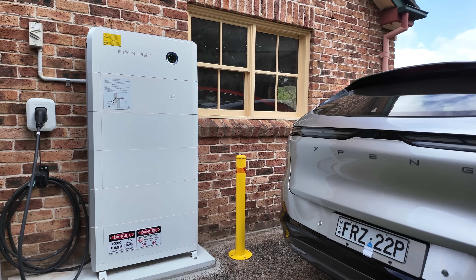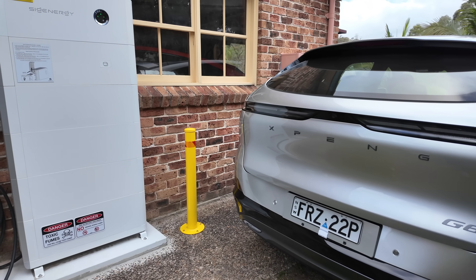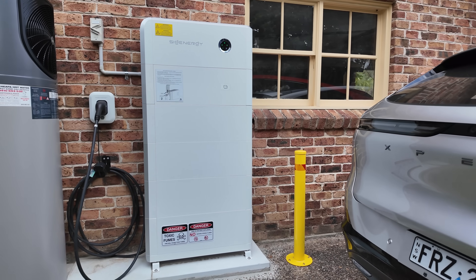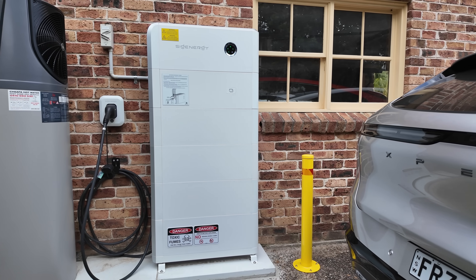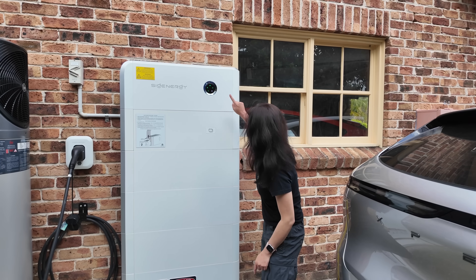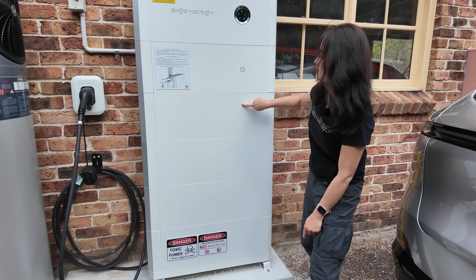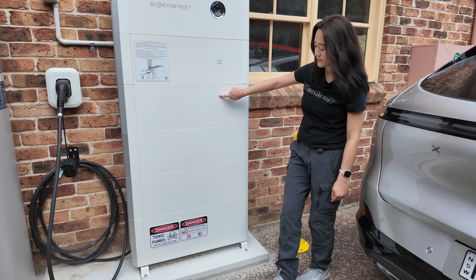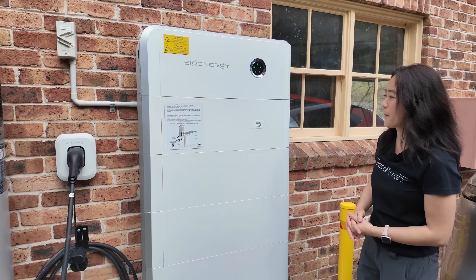We are in a viewer's house in Northern Sydney. That's the XPENG G6 that we have on loan, and next to it is the viewer's Sigenergy battery stack. As you can see, there are five modules, very similar to our battery at home, with the inverter on top. The bottom four are batteries — one, two, three, four battery modules. They're eight kilowatt hours each, so a maximum of four times eight, 32 kilowatt hours. And then the fifth one is different to ours — that is the DC charging module.